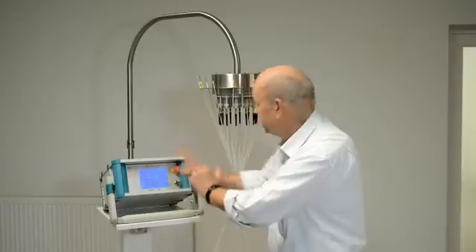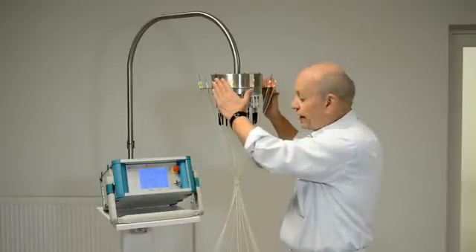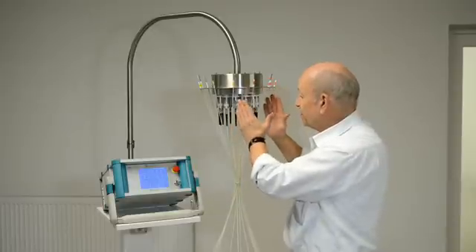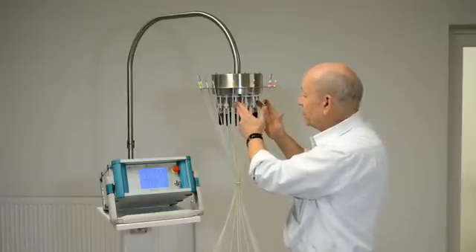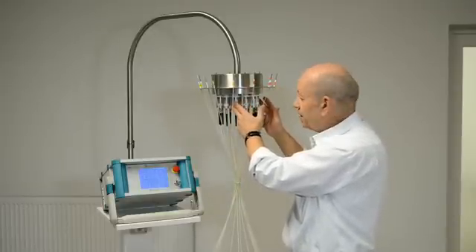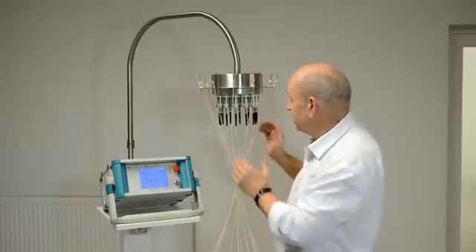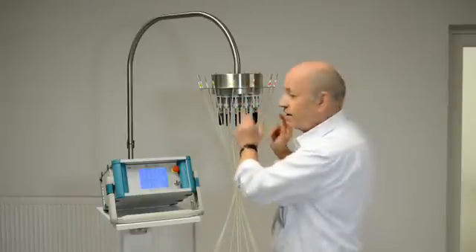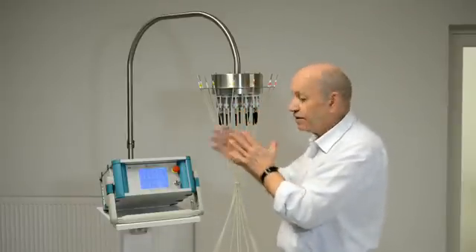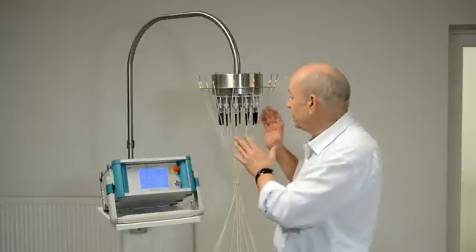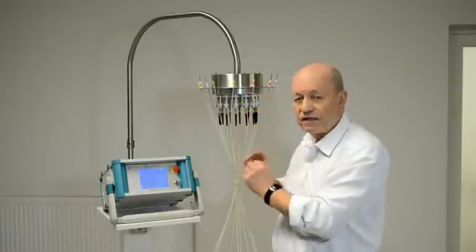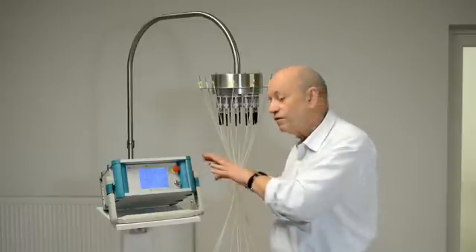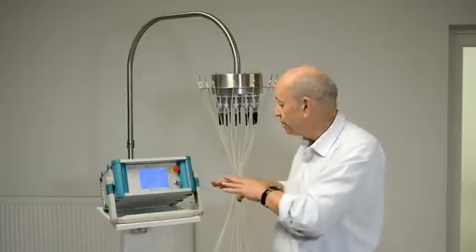The metal head carries the laser modules and can be turned. You see on the laser modules are attached the fiber optic cables, and at the end we see the metal laser needles which are attached on the body and deliver the special laser beams for the different points.